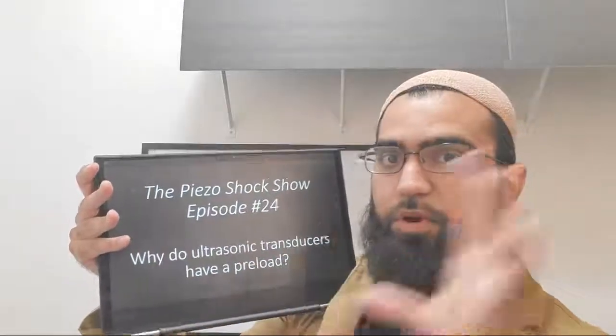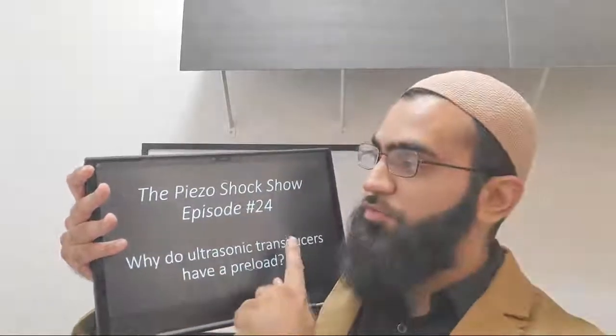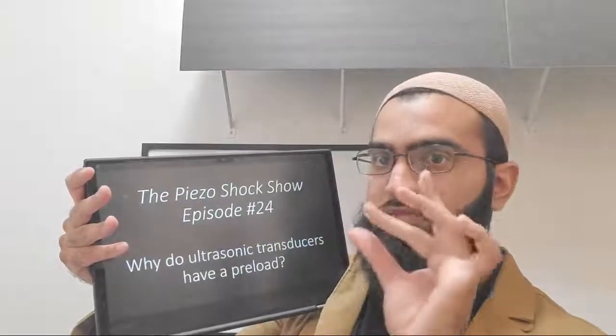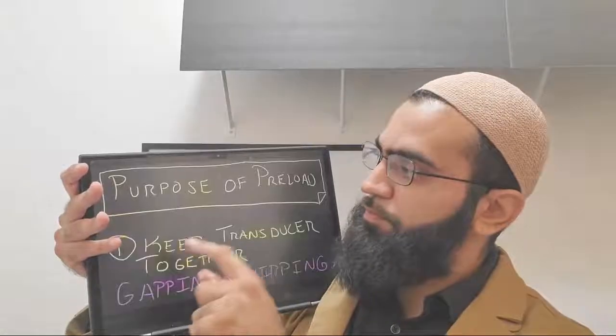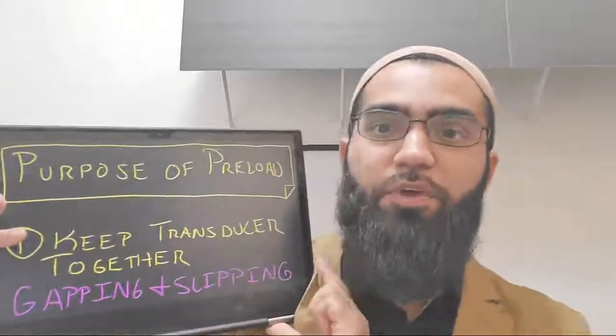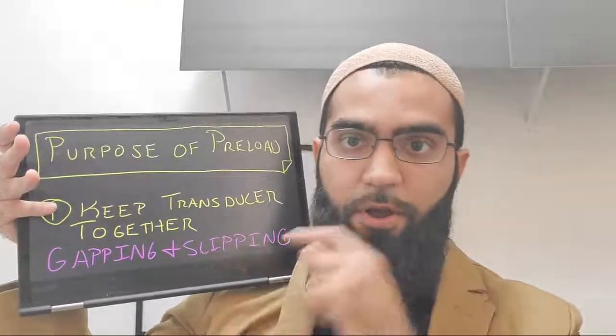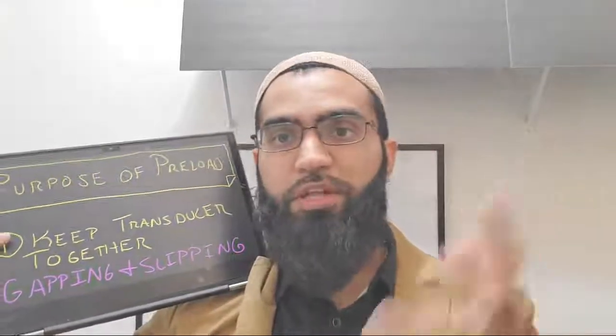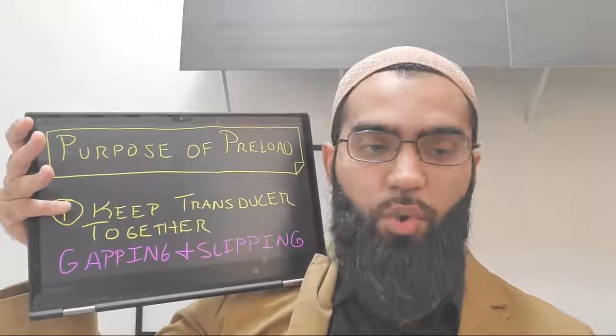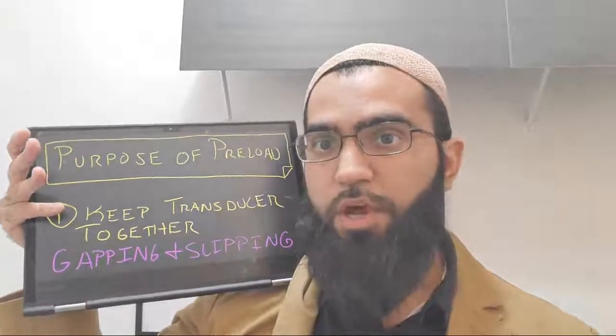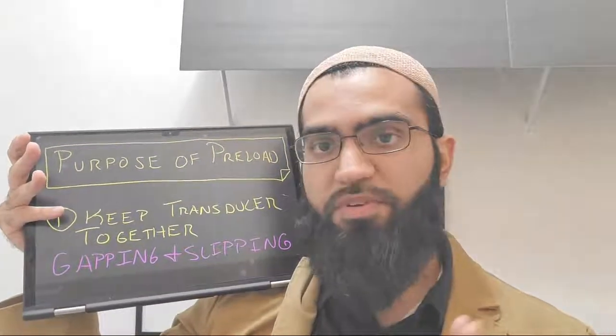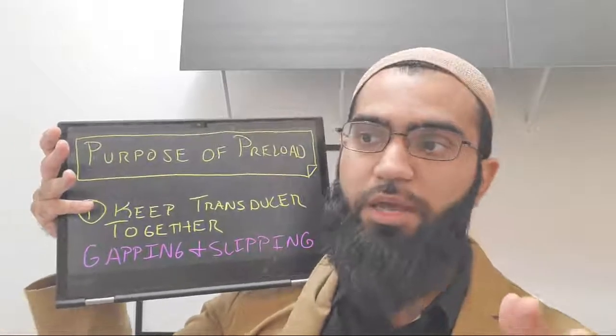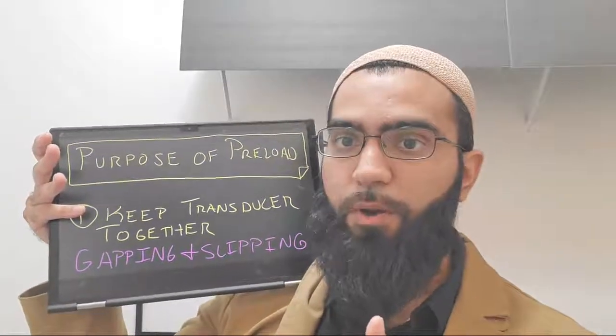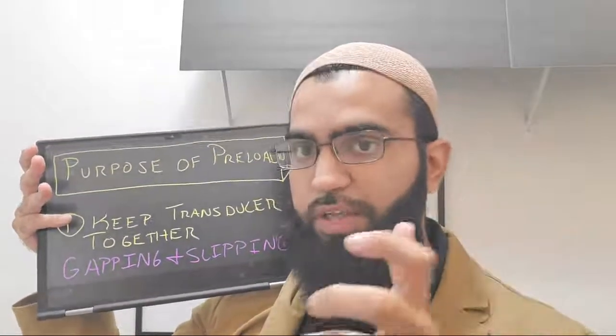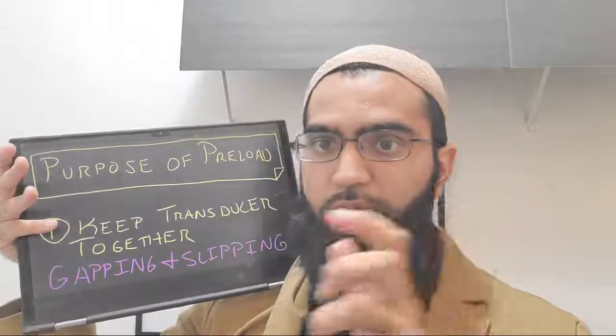So we're answering, why do ultrasonic transducers have a preload? Compressive bias, you could say, compressive stress bias. The first reason is to keep the transducer together. This is especially true in a bolt-clamped transducer, where you sometimes have epoxy, but the primary purpose of the epoxy is not to keep the transducer together. Rather, the bolt clamp mechanism is doing that.